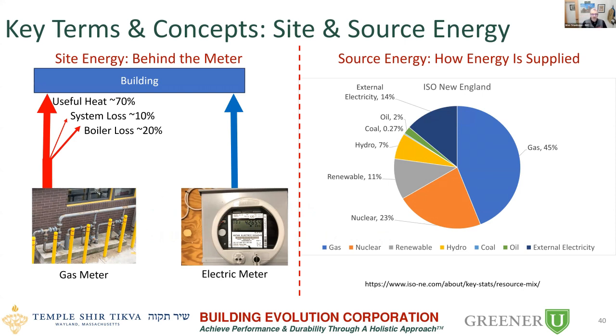Site energy is anything behind the meter, what's in your building, after your electric or gas meter, or even coal delivered to your building. That's your site energy. For example, if you have a boiler, you're going to lose some of the energy burned from the gas, it just goes up the flue as boiler loss. The system itself, going through the building, overheating, other inefficiencies, also loses energy as system loss. You'll maybe have about 70% of that natural gas burned in the boiler actually becoming useful heat, and that can be measured and calculated on site as the site energy.